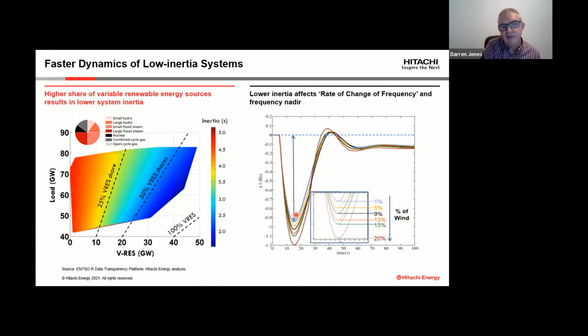Initially, this is literally the rate of change of frequency. We can see how frequency changes with time, and that was described on the previous slide, dependent on the amount of inertia. The UK system is designed to have enough inertia to last for 10 seconds, and it's in that 10 seconds that the balancing and ancillary markets I mentioned previously come in, with some of the commercial arrangements for fast frequency response, which is typically provided by battery energy storage systems now.